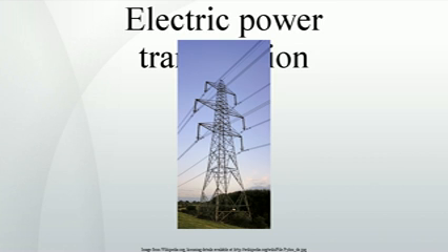For alternating current it was 4,000 kilometers, 2,500 miles, though all transmission lines in use today are substantially shorter than this. In any alternating current transmission line, the inductance and capacitance of the conductors can be significant. Currents that flow solely in reaction to these properties of the circuit, which together with a resistance define the impedance, constitute reactive power flow, which transmits no real power to the load. These reactive currents however are very real and cause extra heating losses in the transmission circuit.